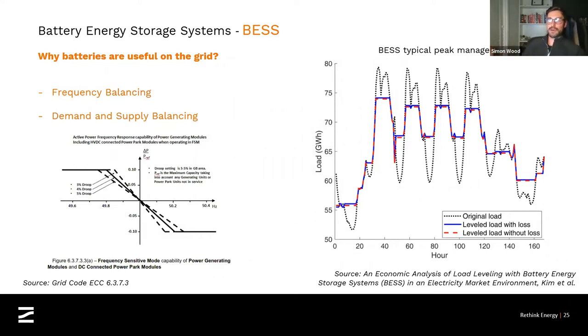That's at a macro level, looking at the UK-wide load for energy or power. What batteries would do is more on a local level, on a more micro scale. But the theory is the same, and that's known as energy arbitrage. And yes, batteries are used for that, but typically it's not the most beneficial use case for a battery. That's where things like frequency services and reactive power capabilities come into play, frequency being the most dominant.